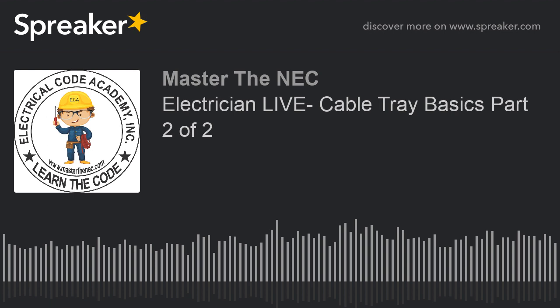Now, for many years, it never said that. It said single conductor cables. But THHN, THWN, XHHW-2 aren't necessarily single conductor cables. They are single insulated conductors. So we did it anyway, but now we have clarity, and they're considered synonymous in the applications here in 392. When they're 1/0 or larger, that is.